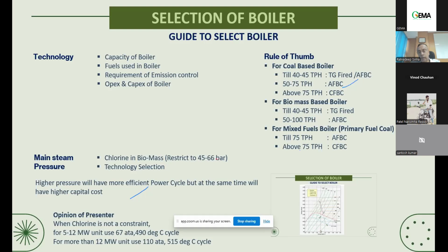Basically, TG fired will be selected for a biomass kind of thing, AFBC for a biomass and coal mix kind of thing. For a higher capacity, 50 to 75, 80 TPH, straight away you should go for AFBC, should not look for TG fired, but still you can look at TG fired if you want to go for a lower capex, but your opex will be higher because the efficiency will be low. And above 75, obviously you should go for a CFBC boiler.